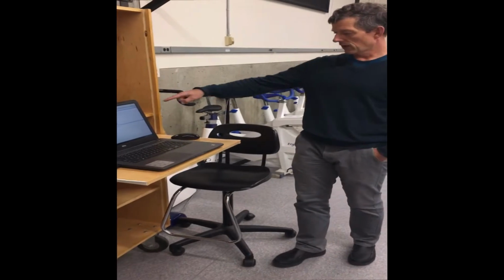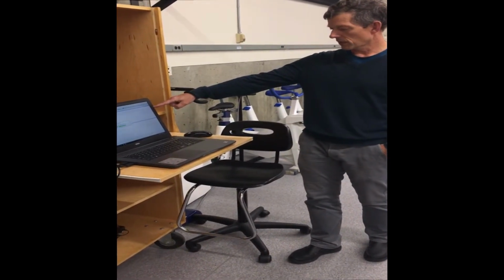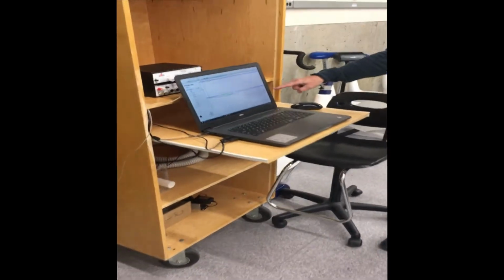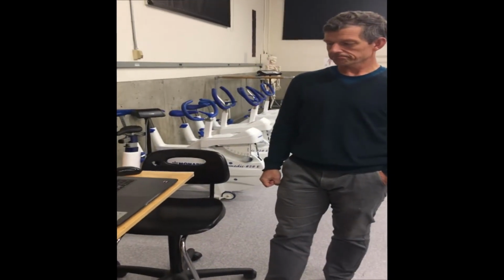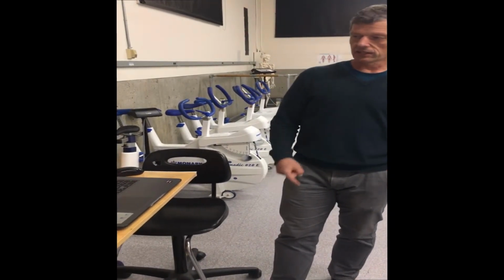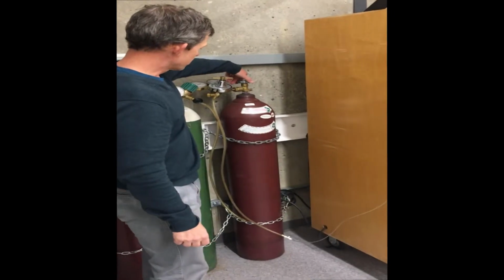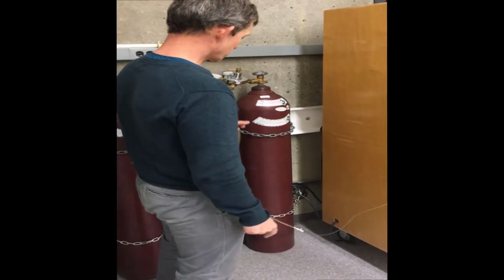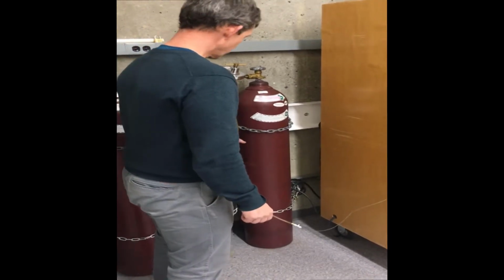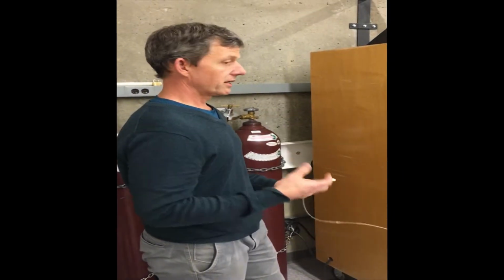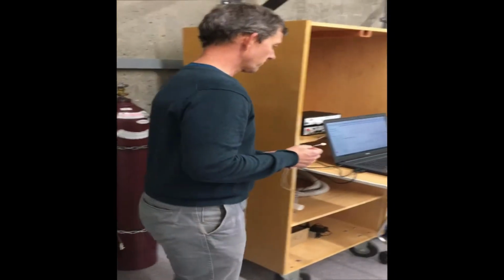And now what it's going to do is analyze the calibration gas, and it's going to do it for 20 seconds. So here you can see how the CO2 has increased. It's approximately 5%, and you can see the oxygen has decreased down to about 15.6%. So it'll sample that for 20 seconds. And when it's done, it'll tell us to turn off the sample gas. So what I typically do is turn the cylinder off first, and then that allows any excess pressure to bleed through. And now I can close this line. And now we're able to sample our gas, and we know that it has been calibrated, and we should get a fairly accurate reading based on our calibration.